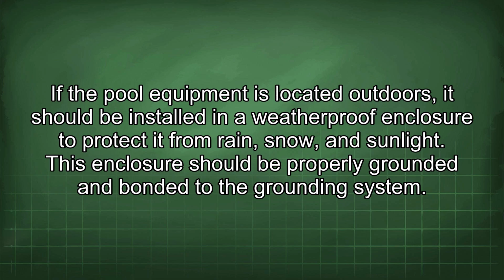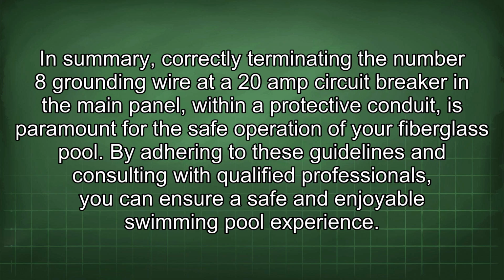If the pool equipment is located outdoors, it should be installed in a weatherproof enclosure to protect it from rain, snow, and sunlight. This enclosure should be properly grounded and bonded to the grounding system. In summary, correctly terminating the number 8 grounding wire to the 20 amp circuit breaker in the main panel within a protective conduit is paramount for the safe operation of your fiberglass pool. By adhering to these guidelines and consulting with qualified professionals, you can ensure a safe and enjoyable swimming pool experience.